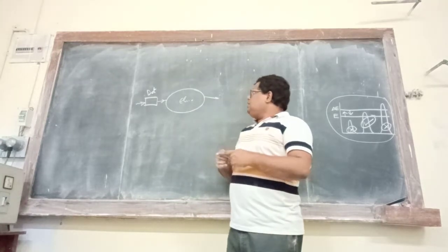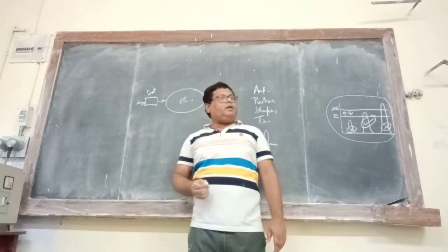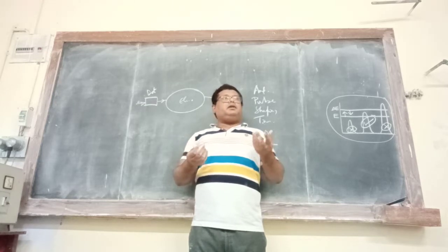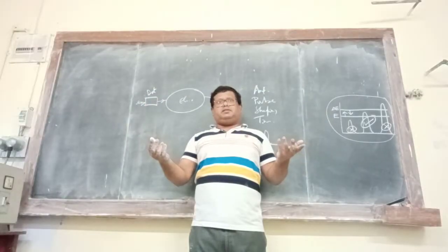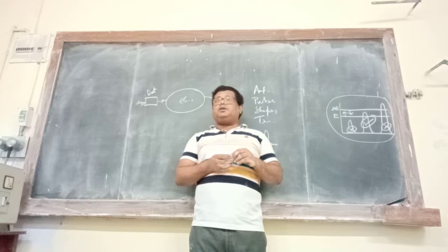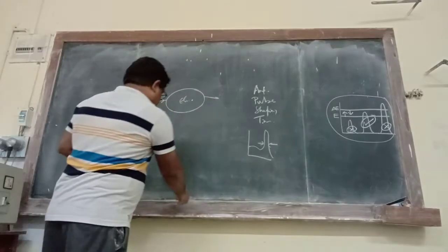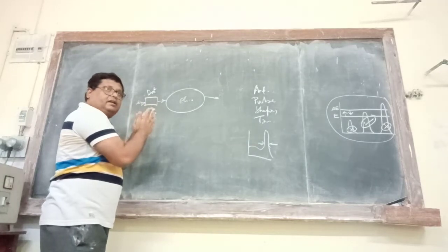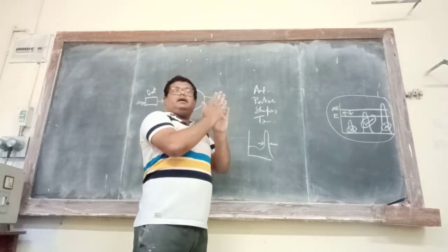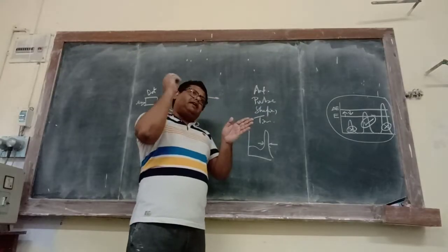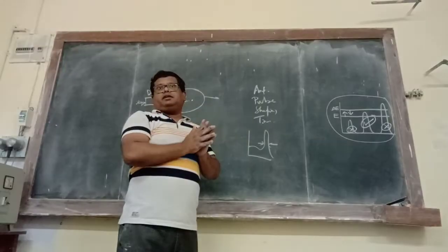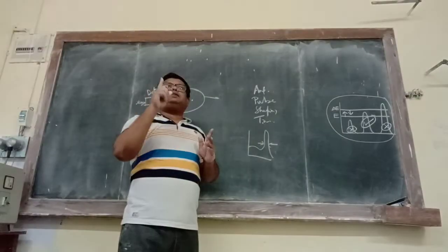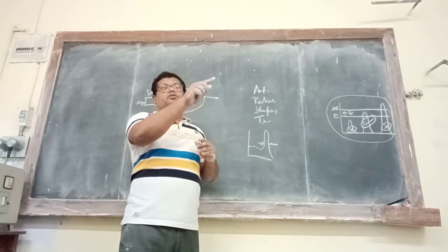You have to understand. Again, if you put a source very close to the detector, what will happen? Count rate will be high. I mean, in 1 second you will get lots of pulses. Do you think it's a good idea, or can something bad happen? The thing is that there is a time for which the detector window opens for detecting the signal. Now in this time, if you put the source very close to it, 2 or more gamma rays will enter, with the same cesium-137 I am using. So what will the detector detect? If 2 gamma rays enter, the detector will say, I have detected a single pulse of value 662 into 2.